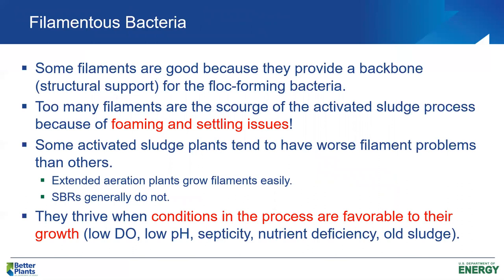The filamentous bacteria are good in that they provide a backbone — a structure for the good floc-forming bacteria to form around. The analogy would be the human body: without a skeleton to hold all our organic mass together, we'd just be a clump of organic matter on the floor. The filamentous bacteria provide structural integrity for the biological floc. Nevertheless, too many filaments means our sludge may not settle in the final clarifier, or we may have foaming in the aeration basin and effluent. Too many filaments can be a huge problem in the activated sludge process.